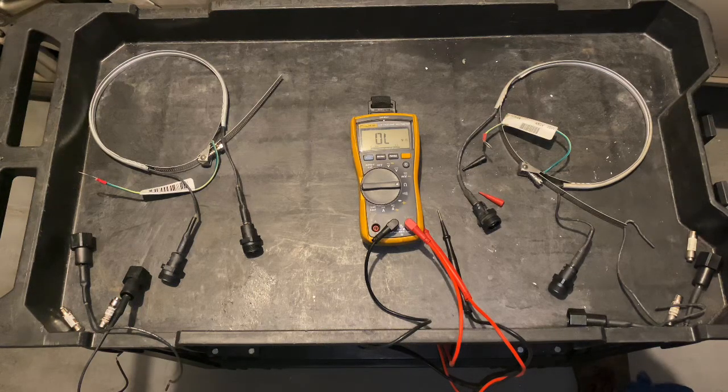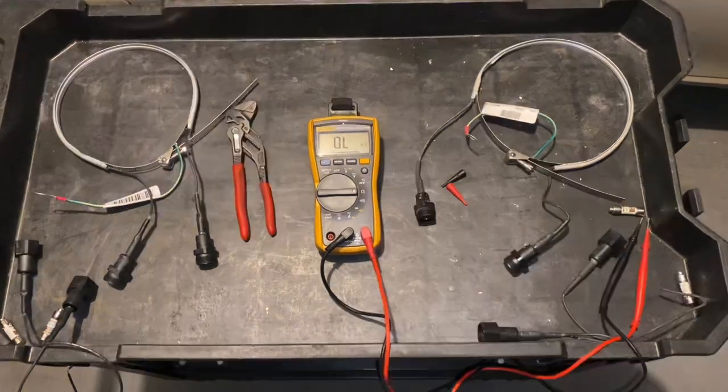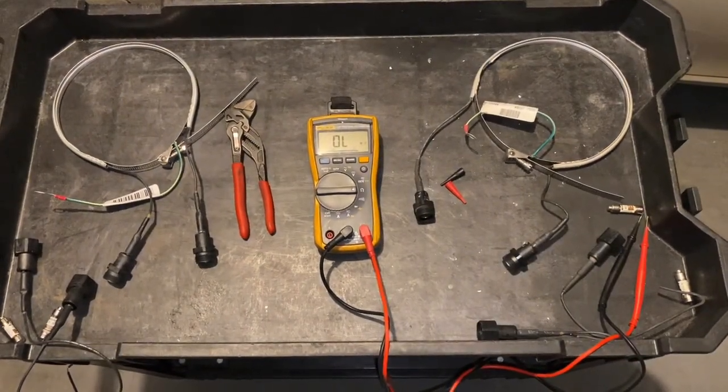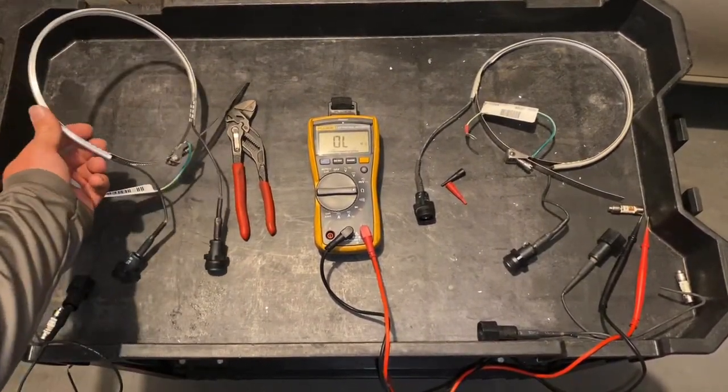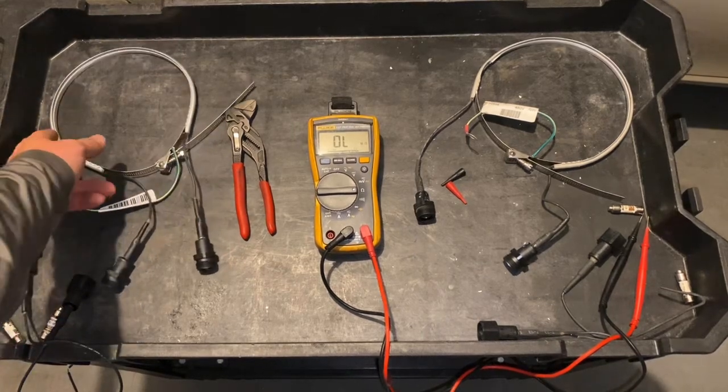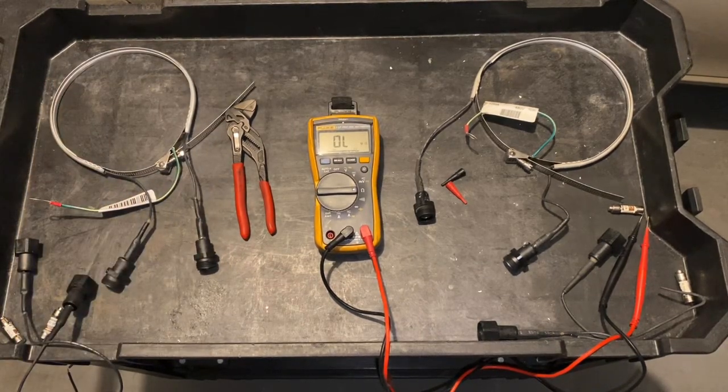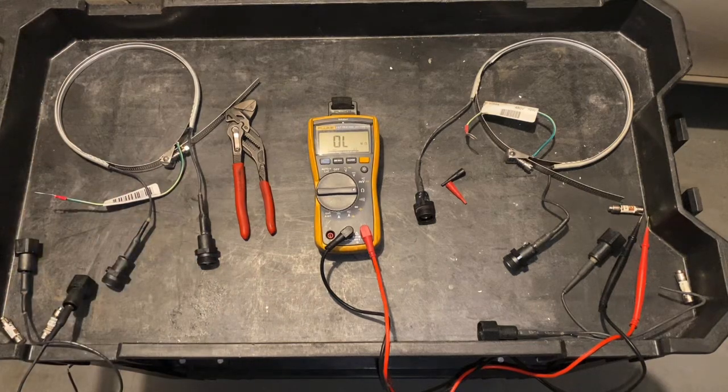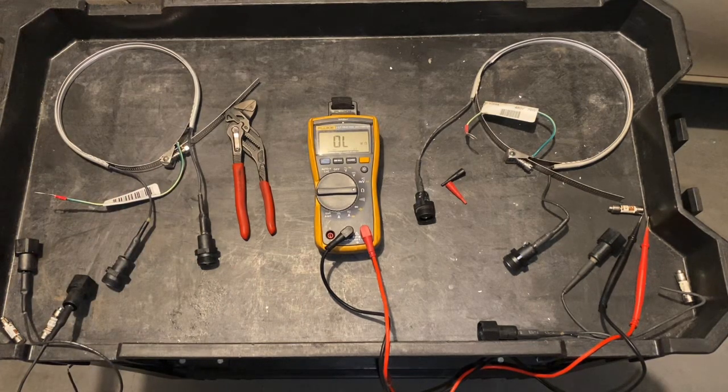Yeah, I hope this helps. A couple more notes. Of course you can do a touch test on a good crankcase heater. It's going to feel so hot that it's going to feel like it's almost burning you, if not burning you when you touch it.